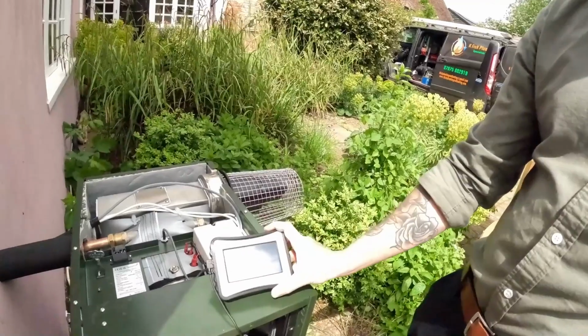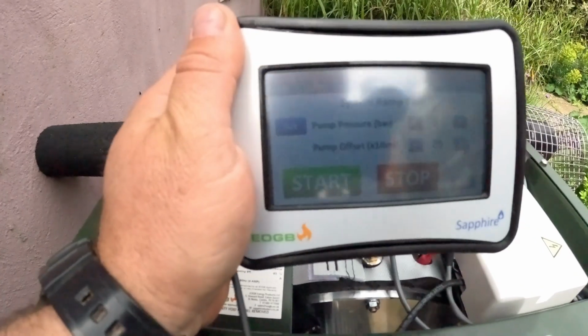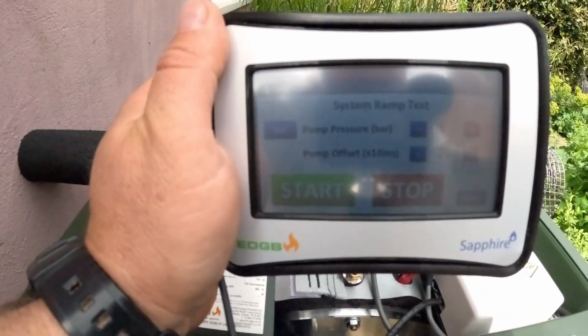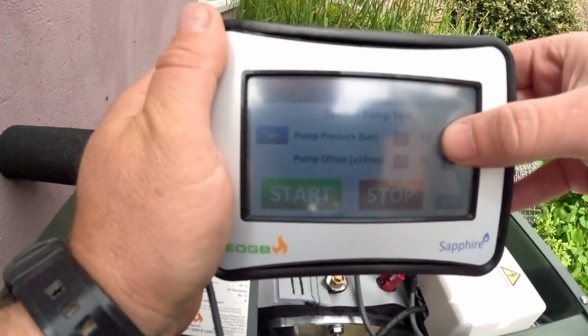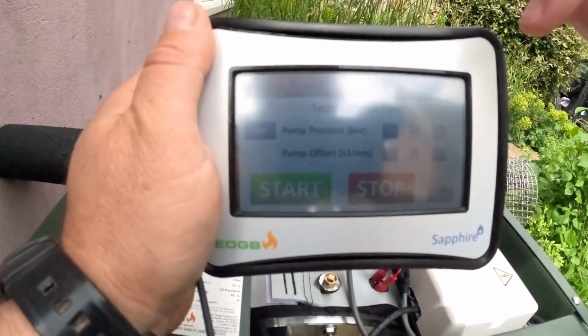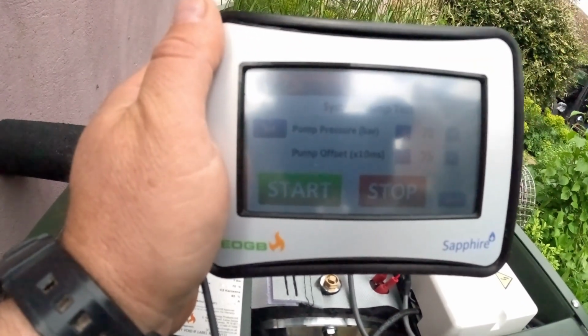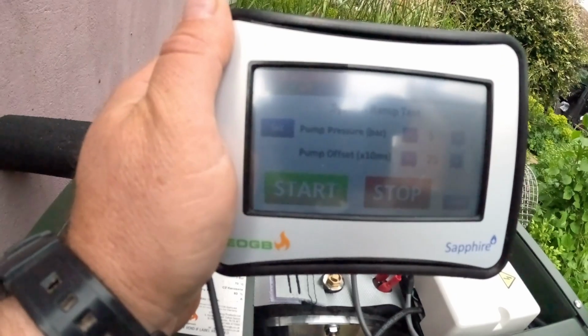Right, so we've got the boiler nice and commissioned. Reece from EOGB's here, just going to run through what this controller actually does. So when we're setting the boiler up, Reece, what do we see from here? Obviously the picture's not fantastic because of the light. The first screen you'll come to is the system ramp test - this screen is ideal once you've commissioned it, so when you turn up to a service you can quickly take this to wherever you want. By adjusting the pump pressure, that's where we get our modulation from the burner. So you take it up to 20, press set, and the burner will drive all the way up. Then if you come back down to 5 and press set, the burner will drive all the way back down - so you can hear a nice smooth modulation range.